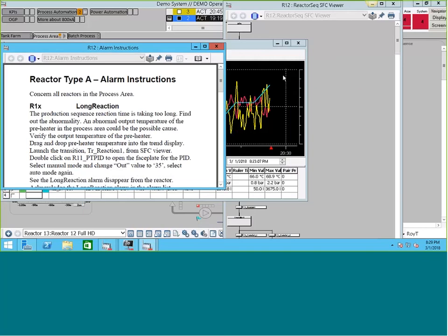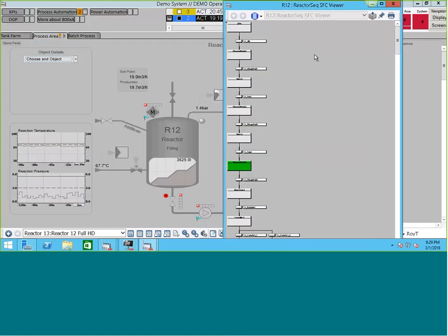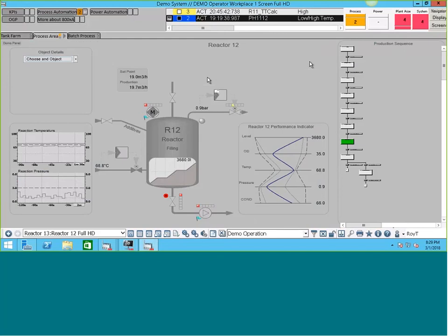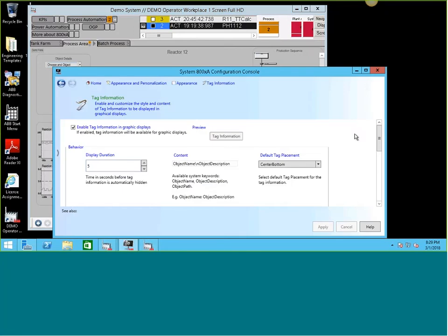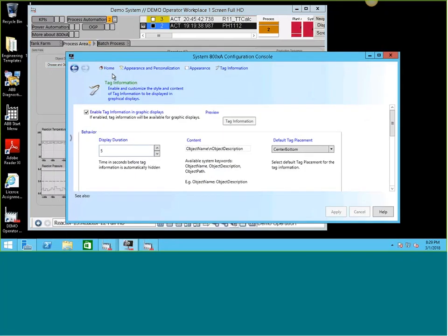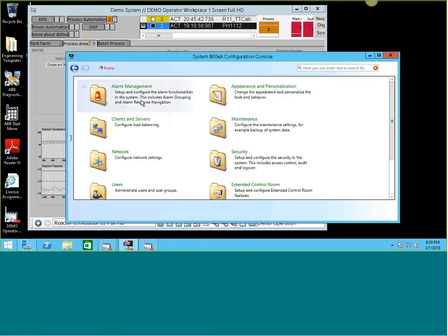Right, and you could set it for a full system for alarm response, and if the aspect just doesn't exist on that object, it just won't open. It won't show. Right, so that way you can set it and it stays for alarm helping and have a bunch of documents, but you don't have it on all tags. It'll still function correctly for those ones that do, and the ones that don't, nothing will open up.